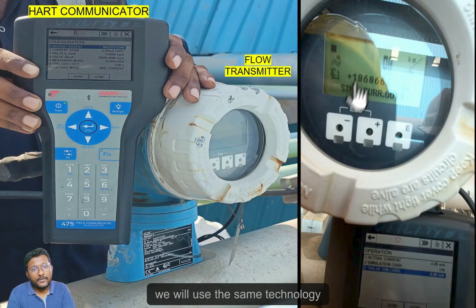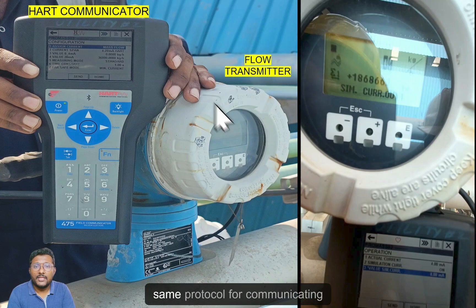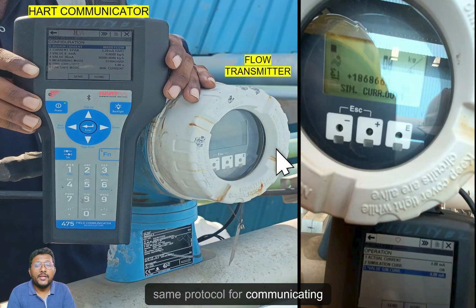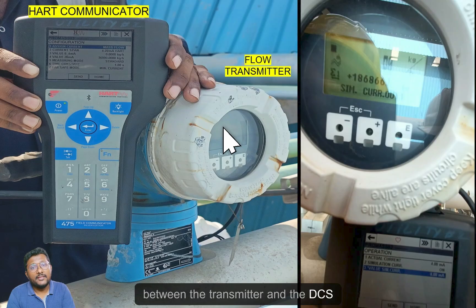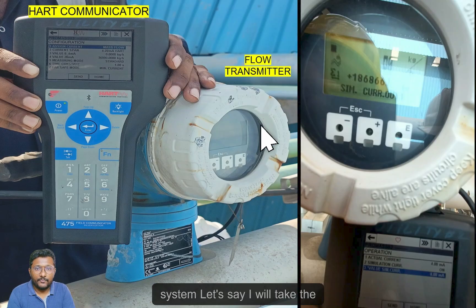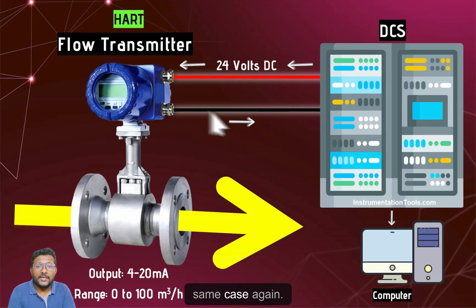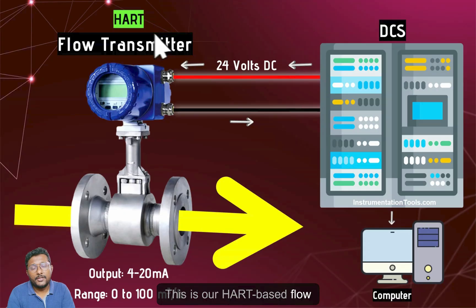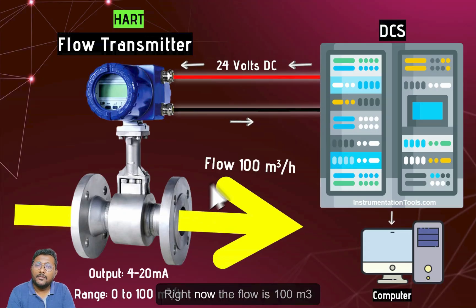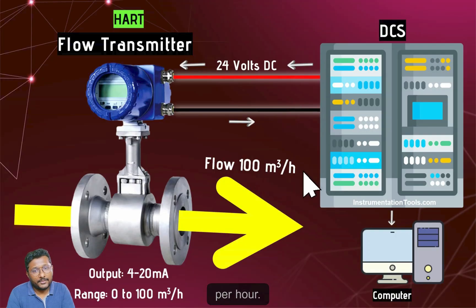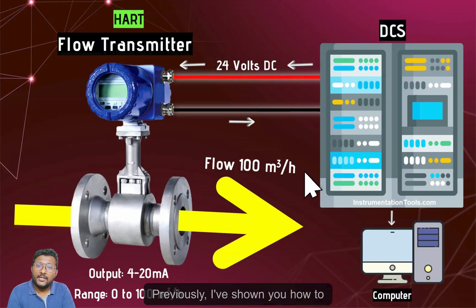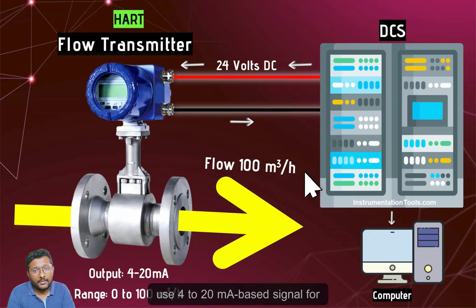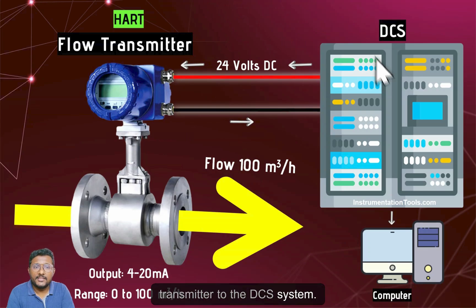We will use the same protocol for communicating between the transmitter and the DCS system. For example, this is our HART based flow transmitter and right now the flow is 100 cubic meters per hour. Previously I showed how to use the 4 to 20 milliamp signal for transmitting this measured flow rate from the transmitter to the DCS system.